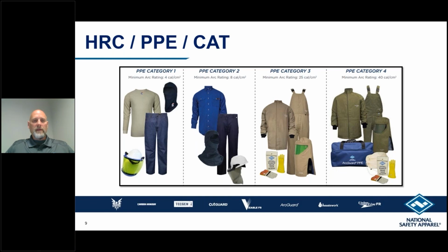So what does that mean? That means that as you get more significant incident energy, you need thicker or more protective clothing. Not always thicker, but typically if you look at Cat 1 versus Cat 4, there's always going to be a thickness that is obvious. Most people in the work environment today are asking for Cat 2 or Cat 4. They're ignoring Cat 1 and Cat 3. And if somebody's in a Cat 1 incident and they're wearing Cat 2 clothing, they are overprotected. And if they're in a Cat 3 incident wearing Cat 4, they're overprotected.